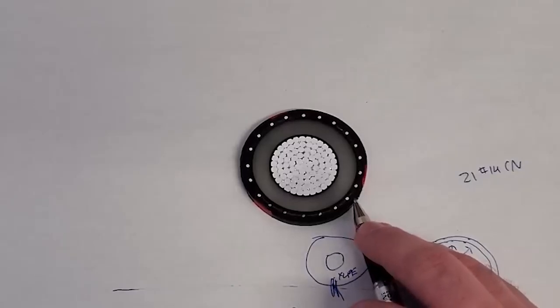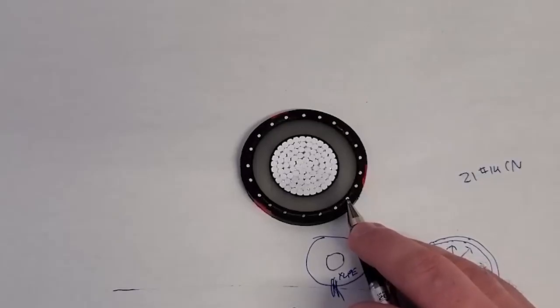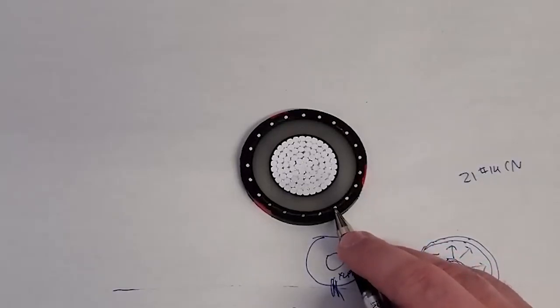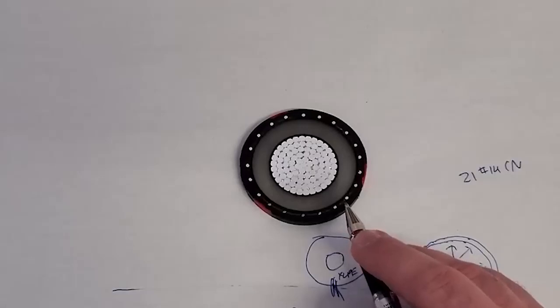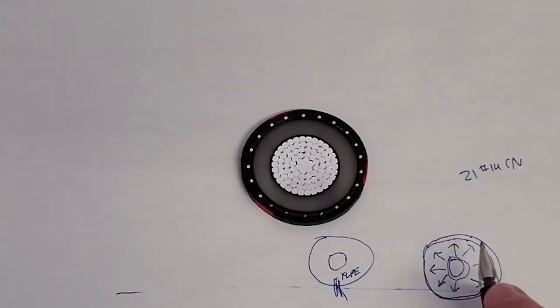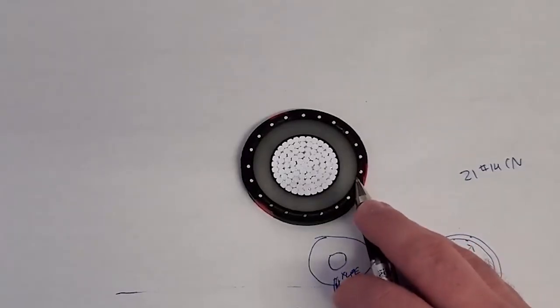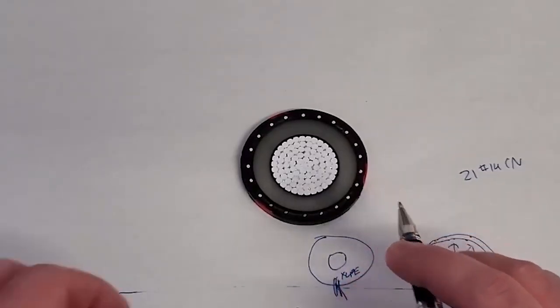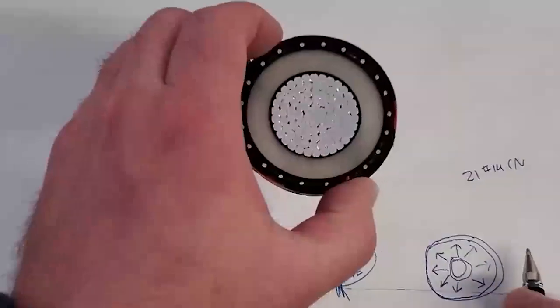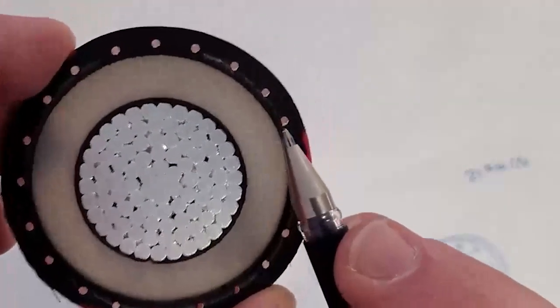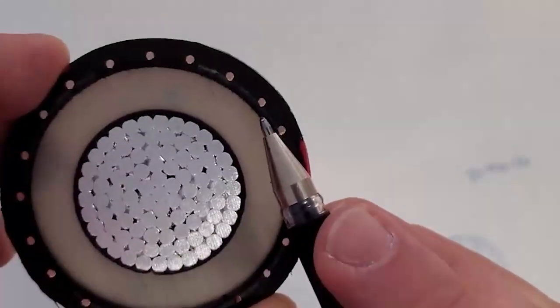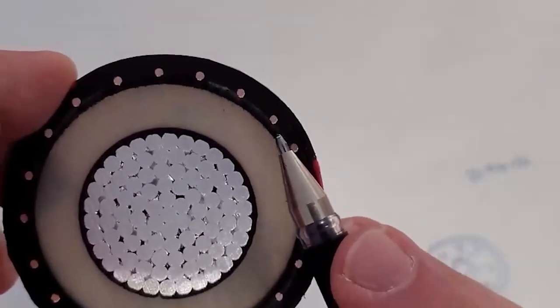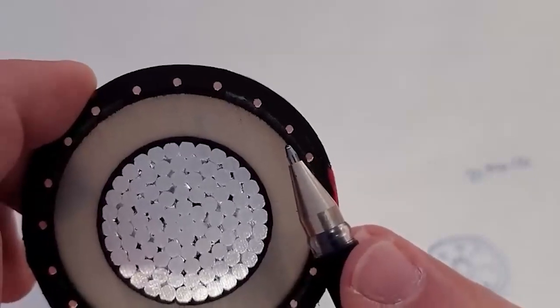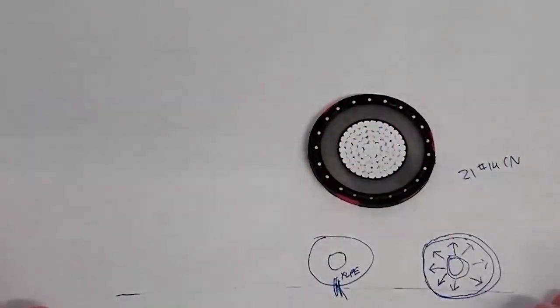We've installed cable without a jacket at all. And that's perfectly fine functionally. What you'll see on the outside are the concentric neutral layers. Nothing wrong with that at all. It's just not wise, in my opinion, because if you have a rock or anything like that that may scrape or puncture through this semicon layer, you're done. It's going to blow up and you have to replace it. You probably see that layer. It's just a slightly different black. Focus. Slightly different black than the LLDPE layer. But that's what that is.